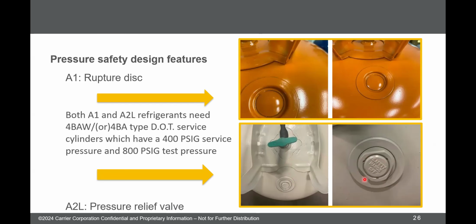Whereas now we're not going to have that. Instead, we have a pressure relief valve on there. So on the new tanks for R32 and 454B, there's a pressure relief valve. The difference being the rupture disc, if it pops, if it ruptures, the whole charge of the tank is gone. It all leaks out, right? The relief valve will open up, dump enough pressure out of the tank to solve the pressure problem so it doesn't blow up, but then it'll shut back off, right? So it's a 20-pound tank. Maybe it opens up, lets some refrigerant off to get to a safe pressure, and now it's an 18-pound tank, and it hasn't completely been a disaster and lost all the refrigerant.